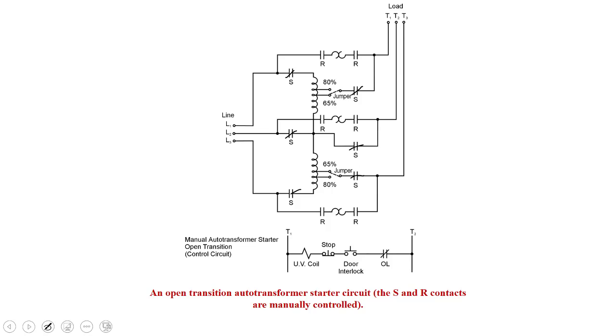And then we'd transition it to run, so that means that the start contacts would open up and the run contacts would close. Now the motor has full voltage. We have one of these in the lab and you're going to see it. It's a manual handle with the door interlock and the stop. So this is the exact diagram of the one in our lab that you guys are going to get to see and try.